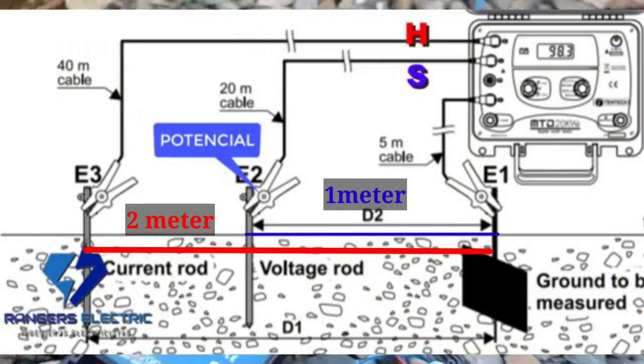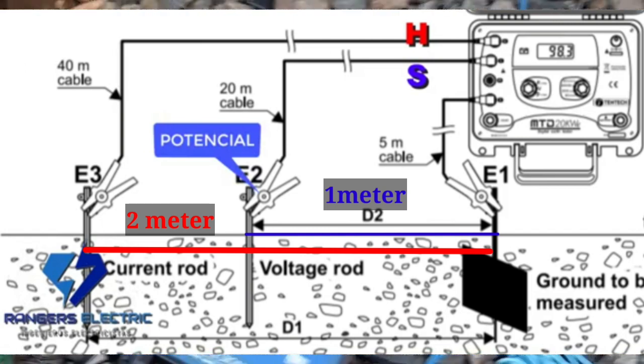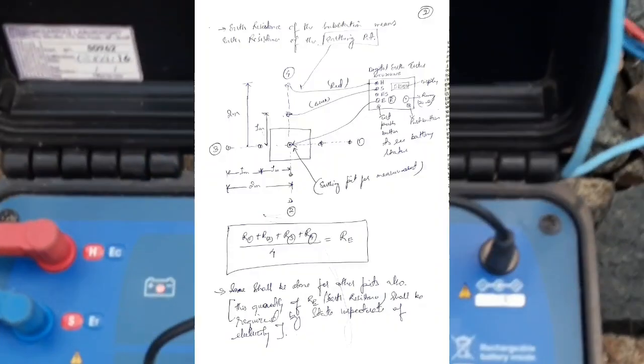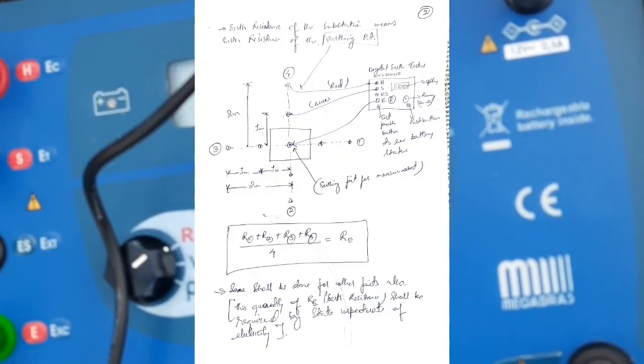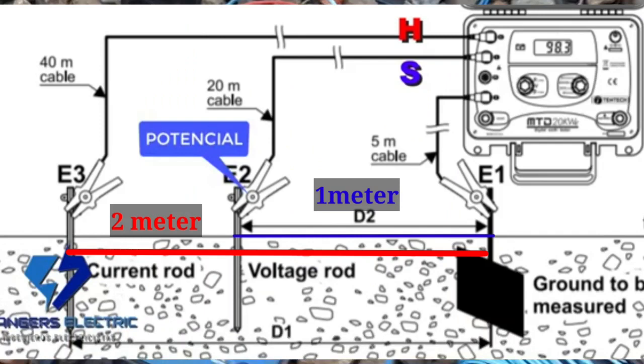The third thing is to connect your H red wire, which is for current injection. You connect the current electrode, the red one, and you have to take it for all the directions: east, north, west, south. The red and blue will be in a straight line from the earthing pit. First connect the red one at a distance of 2 meters from the center of the earthing point under measurement, and the blue one, which is the voltage electrode, at a distance of 1 meter from the earthing pit. This is the standard measurement done by MRT or the Inspectorate of Electricity people when they go for testing or checking. They cannot take 40 meters or 20 meters; they have to keep it at minimum distance. Then the green one, which is the earthing electrode, has to be connected to the center of the earthing pit under measurement.